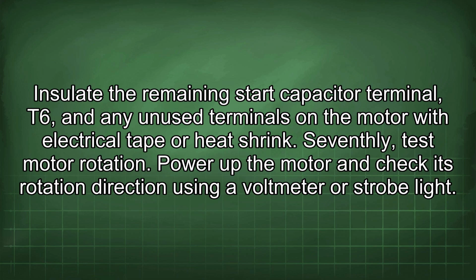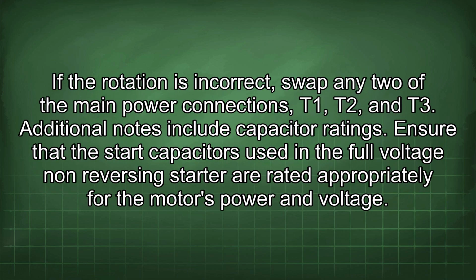Power up the motor and check its rotation direction using a voltmeter or strobe light. If the rotation is incorrect, swap any 2 of the main power connections, T1, T2 and T3. Additional notes include capacitor ratings.